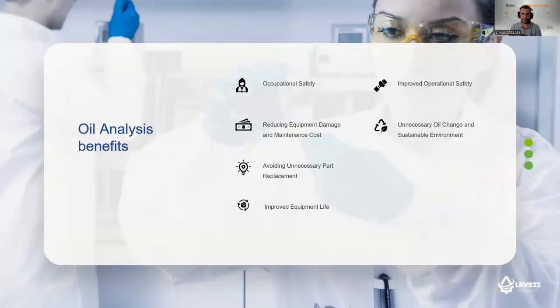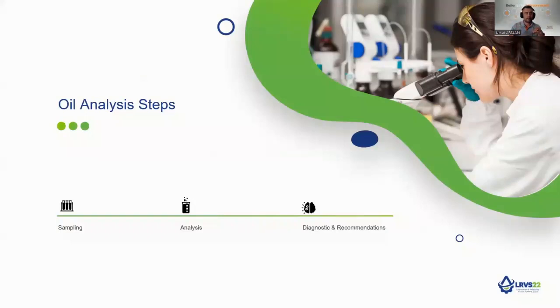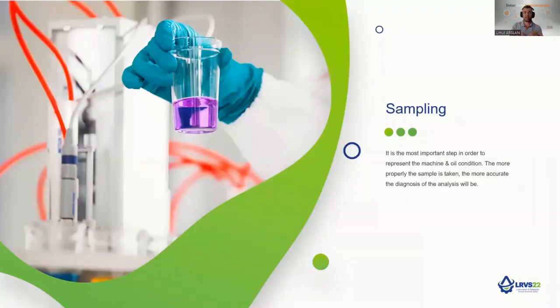Take a look at the oil analysis steps. There are three of them: first of all sampling, then analysis and diagnostic, and finally the report with recommendations. The sampling step is really important, as are all the others, because if you can't take a representative sample, such as without circulating oil, or out of operating temperature, or sampling from the bottom, or after topping up, you'll probably get wrong results. After all, you'll take wrong decisions and finally wrong actions. That's very important.